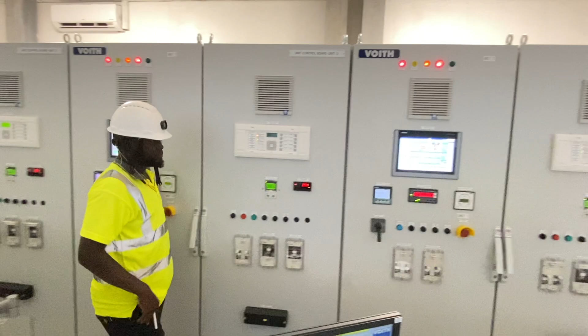We also have the different unit control boards. Our SCADA system communicates with the unit control board, which communicates with the equipment in the field, so there's an exchange of signals from the field to the control board and then to SCADA. Through SCADA we can also operate all pieces of equipment in the field—for example, if I want to open the intake gates, I can send a signal from here without going physically to intake. But I can also go to intake and operate there by using the control level selectors. If the system is in local, I can operate it from the field; if it's in remote, I can operate it from SCADA. So I just switch between local or remote to operate my system.